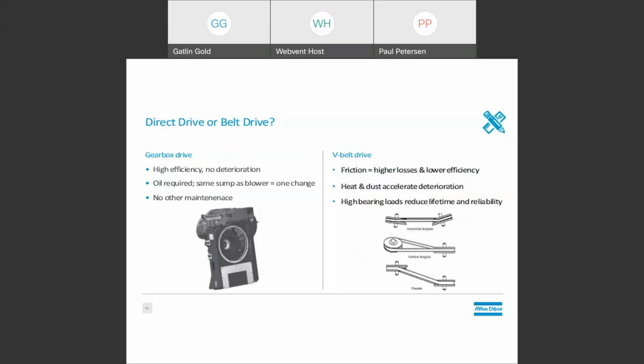Belts are a low-cost solution for drivetrains. You know, generally with blowers, we see three types: direct drive with coupling, direct coupled to a gearbox to increase or decrease speed of the motor, and then V-belt drives to, again, increase or decrease the speed of the motor and blower. Belts are the lowest cost and they don't require lubrication. However, they are easily damaged by oil, grease, abrasive chemicals, and heat, all of which are found in wastewater plants. Gates Corporation is one of the largest manufacturers of belts in the world, especially in North America.